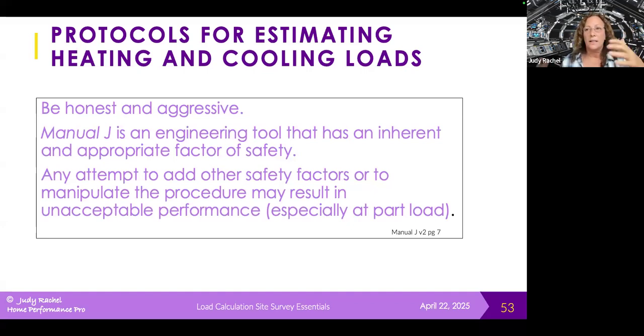Most of my building stock is basically right around sea level. It's very rarely above 1,000 feet. So I'm able to use the constant 1.08 for my specific heat carrying capacity of air. If I was doing it at a different altitude, I would still use the 1.08, and then I would apply those correction factors. Now, the Manual J calculation procedure uses 1.1. So they round up. They don't go all the way out to the hundredths. They round up to 1.1 and only go out to the tenths.